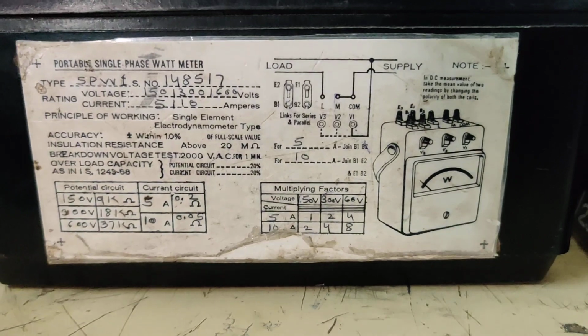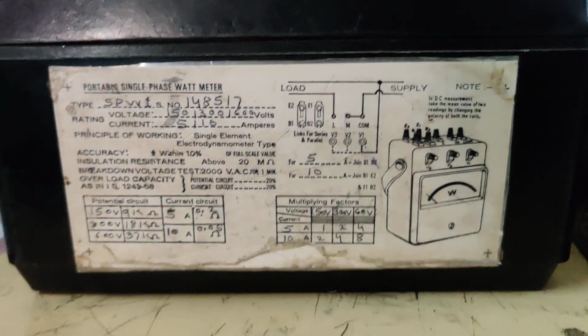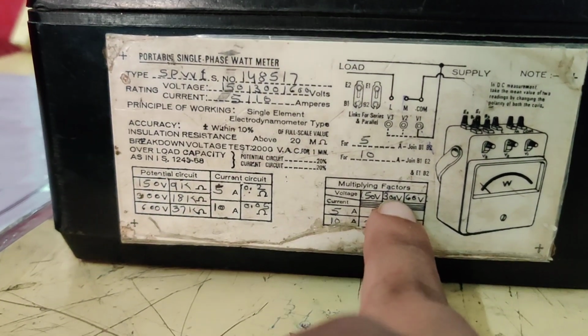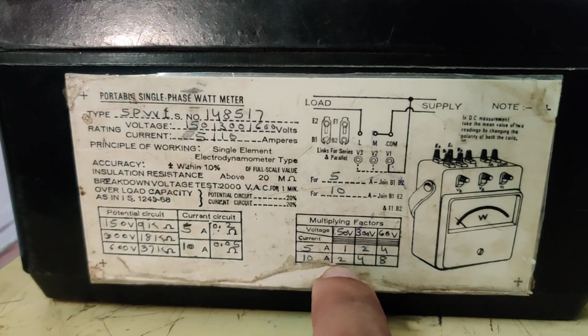So how is the multiplying factor calculated? We have two methods. This particular wattmeter has two ratings: one is 300 volts and 5 ampere, and simultaneously on the secondary side it is 150 volts and 10 ampere. So on both sides we have a multiplying factor of 2.